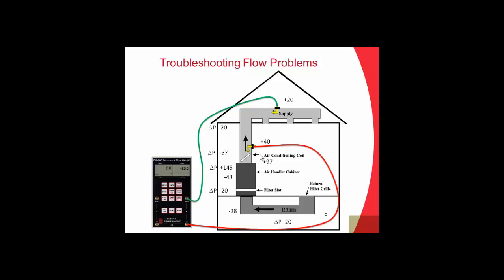It's kind of counterintuitive, but the lower the pressures, the lower the external static pressure, the more that fan is going to be able to move. If you don't have any ductwork attached to it, there's going to be very little change in pressure across that coil. And once we start adding all these restrictions, on the supply side, this 97 is the additive restrictions of all of the ductwork, including the coil, everything on the supply side. And the highest pressure on the return side is going to be after the furnace filter, closest to where the fan is. And that's the additive of all of the return side.